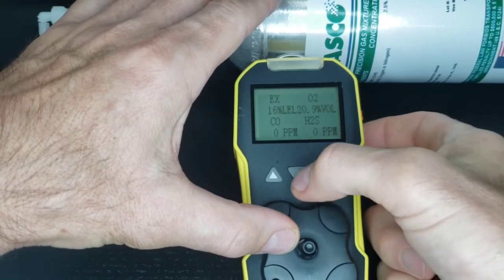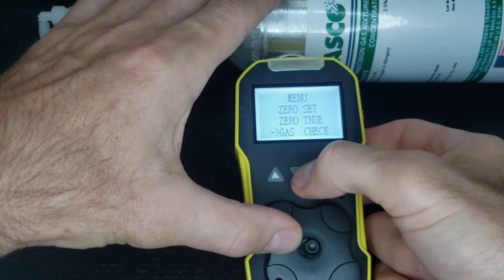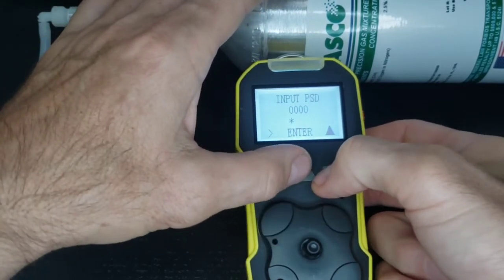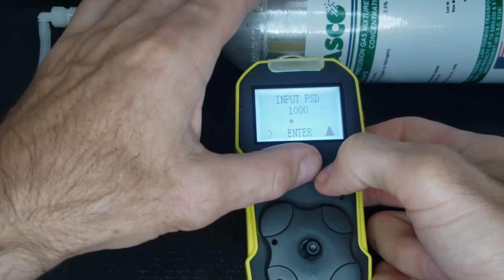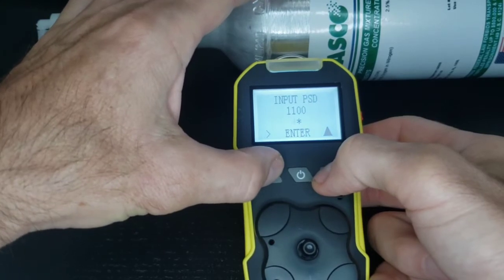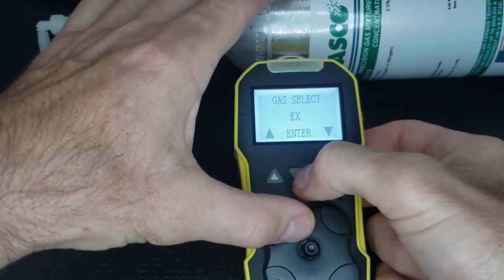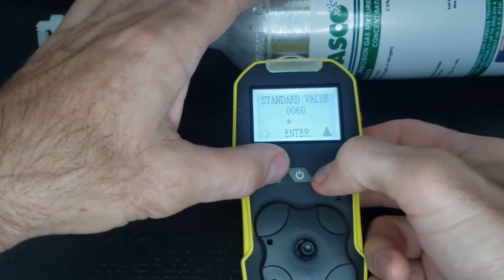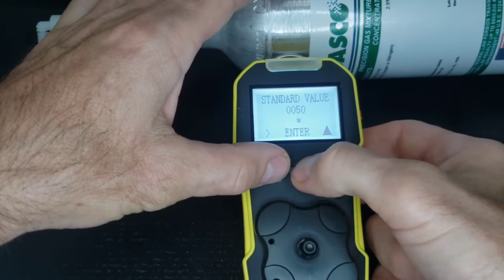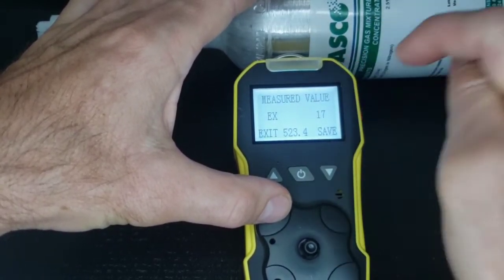So what do we do? Press Enter, go down to dash-check, which means we're going to be calibrating it to a span gas. Press the passcode — it's 1, 0, 0, 0. Press Enter. The standard value that we're putting in — I know it's 50, so it's entering 50. And that tells the detector instead of reading 17, it should be 50.